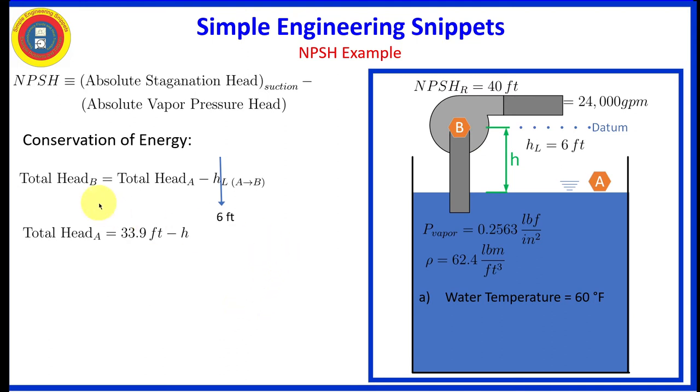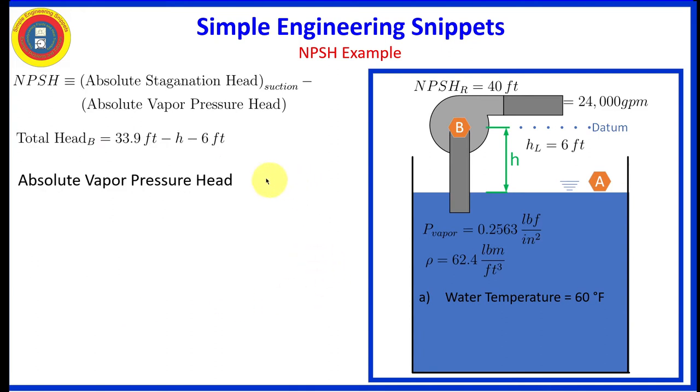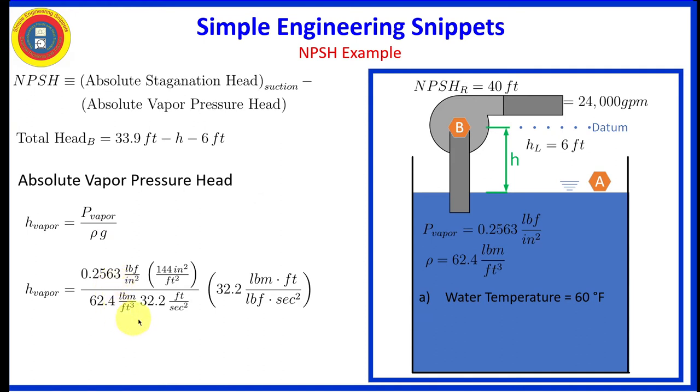Okay, now let's go back to the conservation of energy. Total head of Bravo is equal to total head of Alpha minus the head loss. So plugging that in, we get this equation for the total head of Bravo. And that's good, but we still need to determine the absolute vapor pressure head. It is determined by dividing the vapor pressure by rho G, the density times the gravity. So let's do that. You'll notice the conversion factors. And once again, with these English engineering units, we're going to need G sub C to get the units to work out. And we do that, we get the vapor pressure is equal to 0.592 feet.